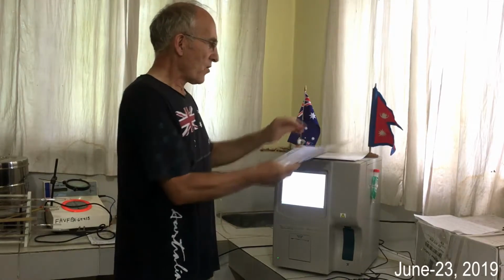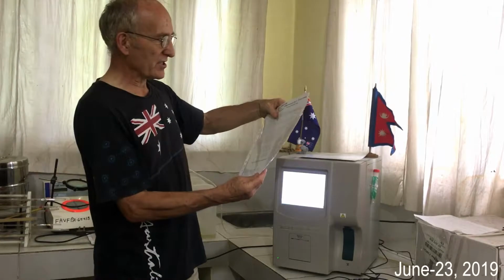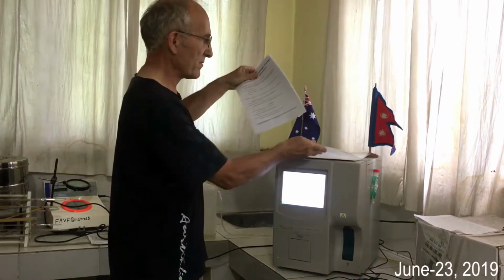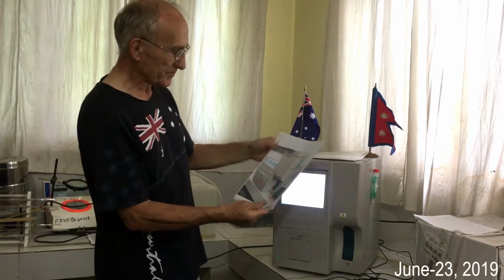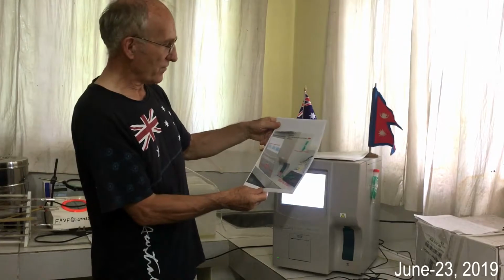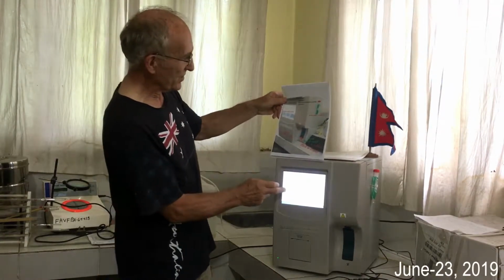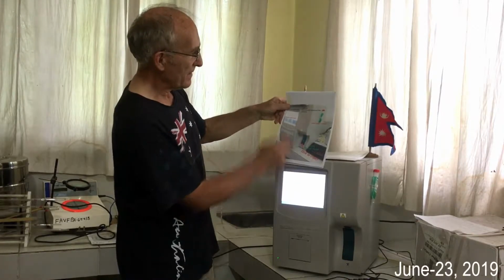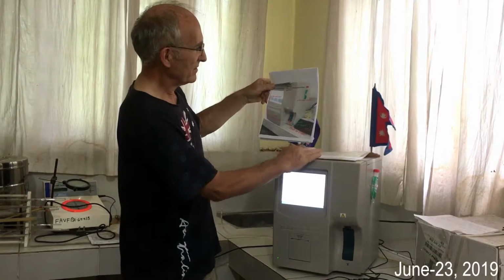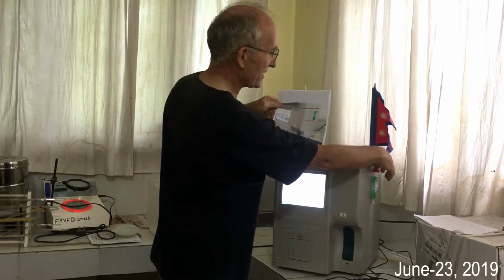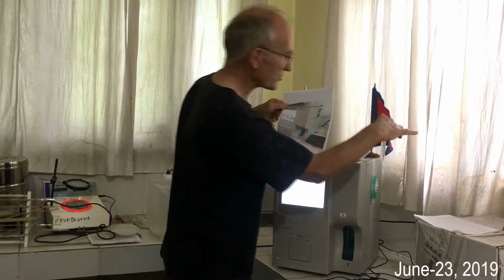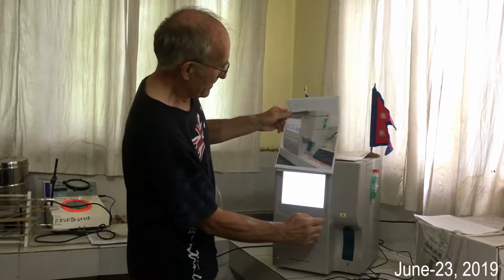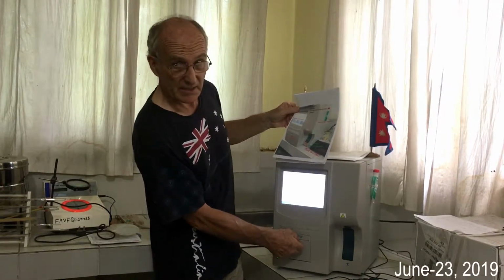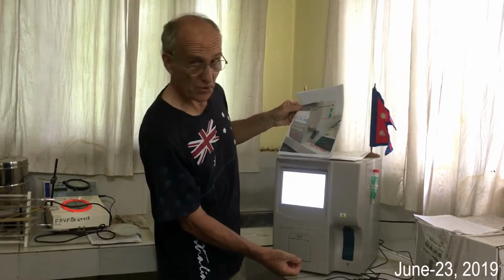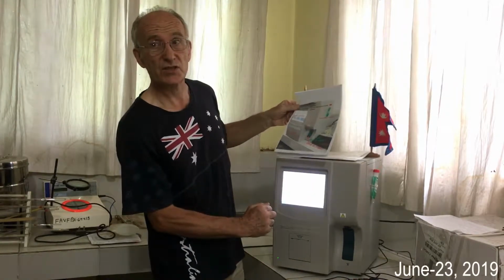On top of the machine, there should always sit this set of instructions. The set of instructions are here to remind people how to use the machine. On the back is a photograph of the machine giving the different parts. So this is the screen which gives you the results. The manual always sits on top of the machine. Round the side of the machine, the probe cleaner is kept in this solution here. So it's always put back here so that it doesn't get lost. That's the probe cleaner. The report comes out here printed in thermal paper. You can either print off the results or you can take a photograph of the screen on your smartphone.